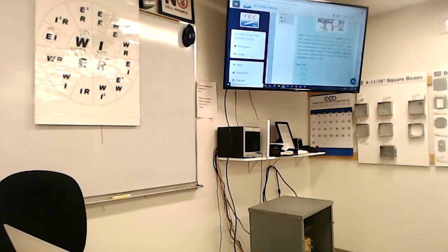That's a single box. We're going to put 2 boxes together. 2 times 18 is what? 36. Okay. That means in order to make that 30 cubic inches work, that's the only box I can put 30 cubic inches in.